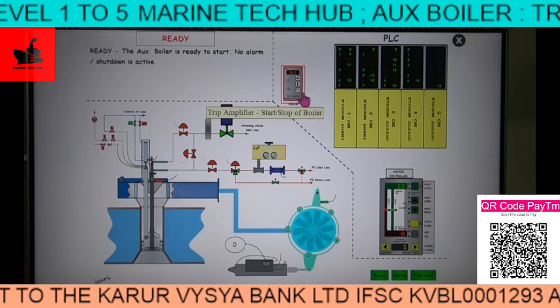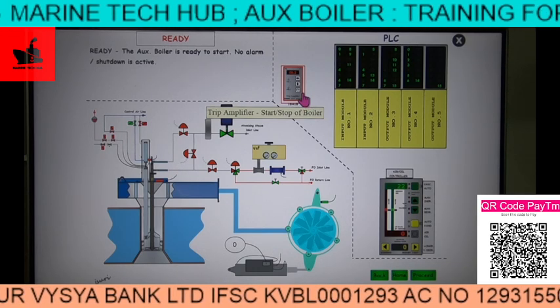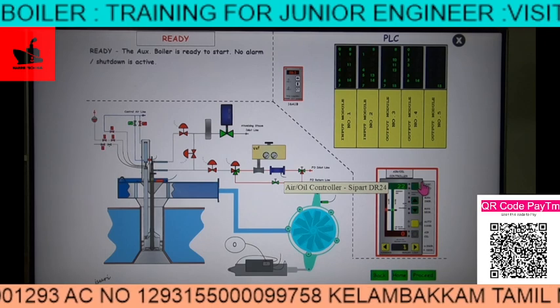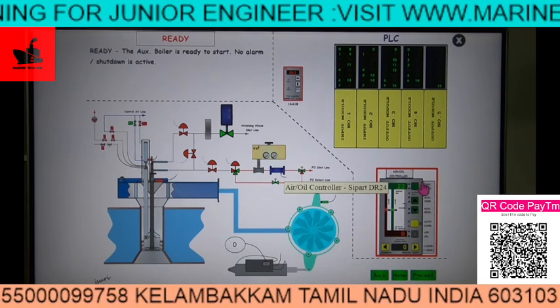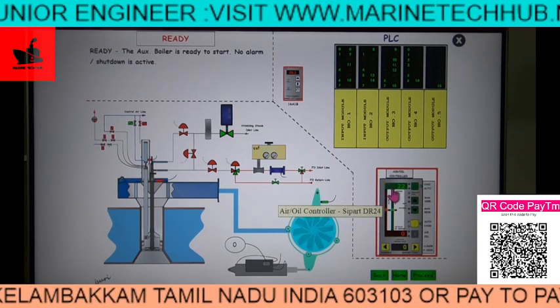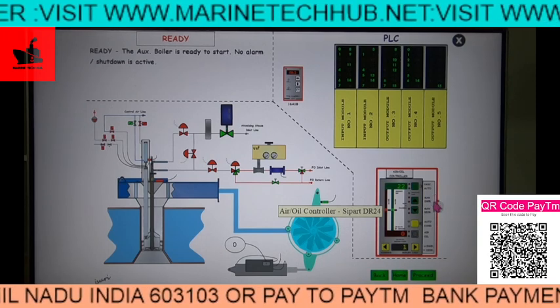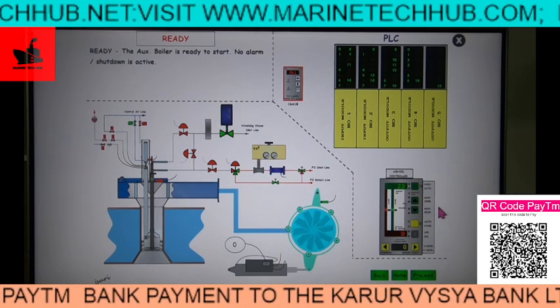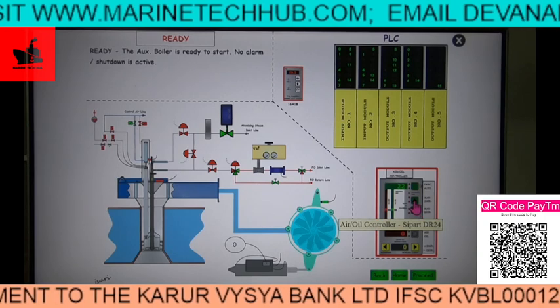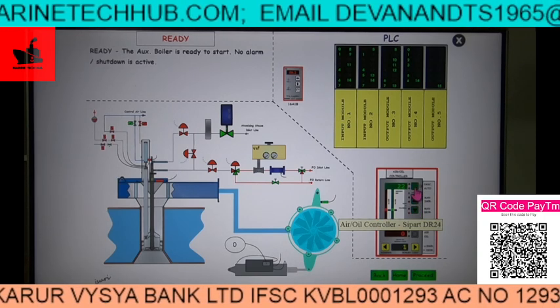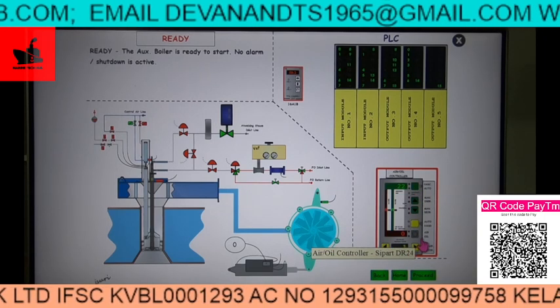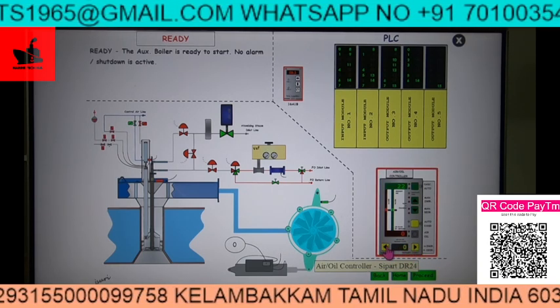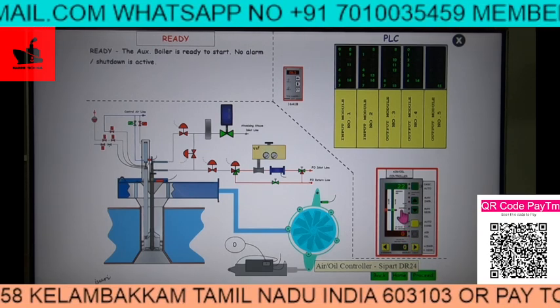We have a component here called the trip amplifier, which will trigger for the start and stop of the boiler. Then we have the air-oil controller, which is made by Siemens — this is the DR24. With this, you can keep it on auto mode or hand mode. You can increase or decrease the settings using the buttons. You can also switch between cascade and auto. This air-oil controller is very important.